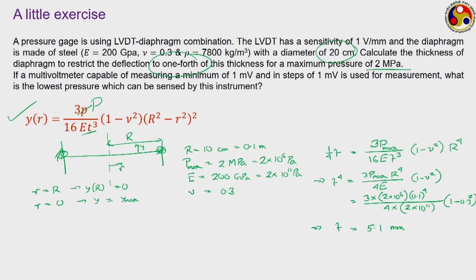That should be the thickness of this diaphragm, so that the maximum deflection corresponding to this 2 megapascal maximum pressure is restricted to 1/4 of this 5.1 millimeter. This way we can calculate the thickness of the diaphragm, or in other words design a diaphragm for a given maximum load.